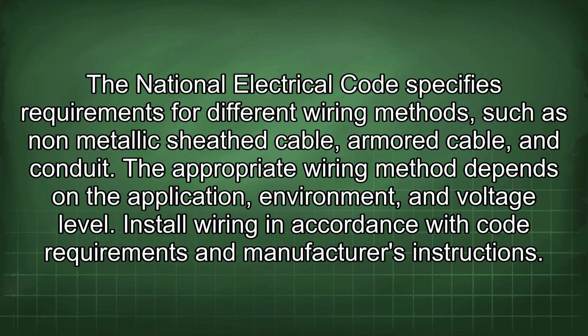Wiring methods are the various ways in which electrical conductors are installed and protected. The National Electrical Code specifies requirements for different wiring methods, such as non-metallic sheathed cable, armored cable, and conduit. The appropriate wiring method depends on the application, environment, and voltage level. Install wiring in accordance with code requirements and manufacturer's instructions.